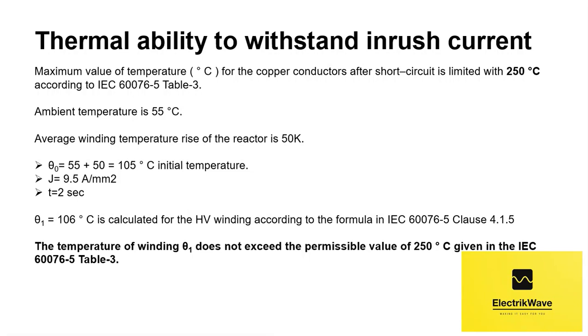Average winding temperature rise of the reactor is 50 Kelvin. Theta_0 equals 55 plus 50 equals 105 degrees Celsius initial temperature. J equals 9.5 ampere per mm². T equals 2 seconds. Theta_1 equals 106 degrees Celsius, calculated for the HV winding according to the formula in IEC 60076-5 clause 4.1.5. The temperature of winding theta_1 does not exceed the permissible value of 250 degrees Celsius given in IEC 60076-5, table 3.